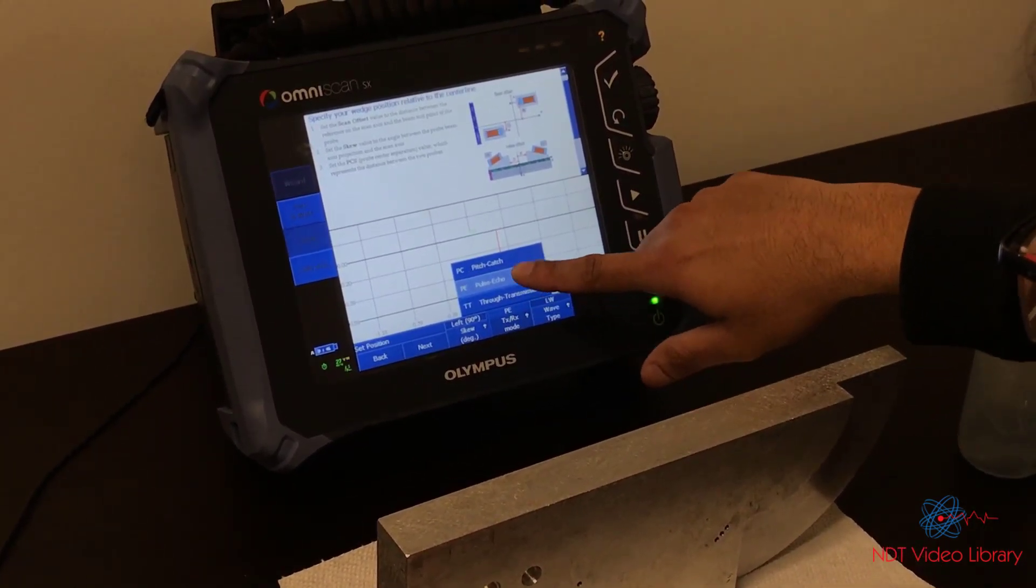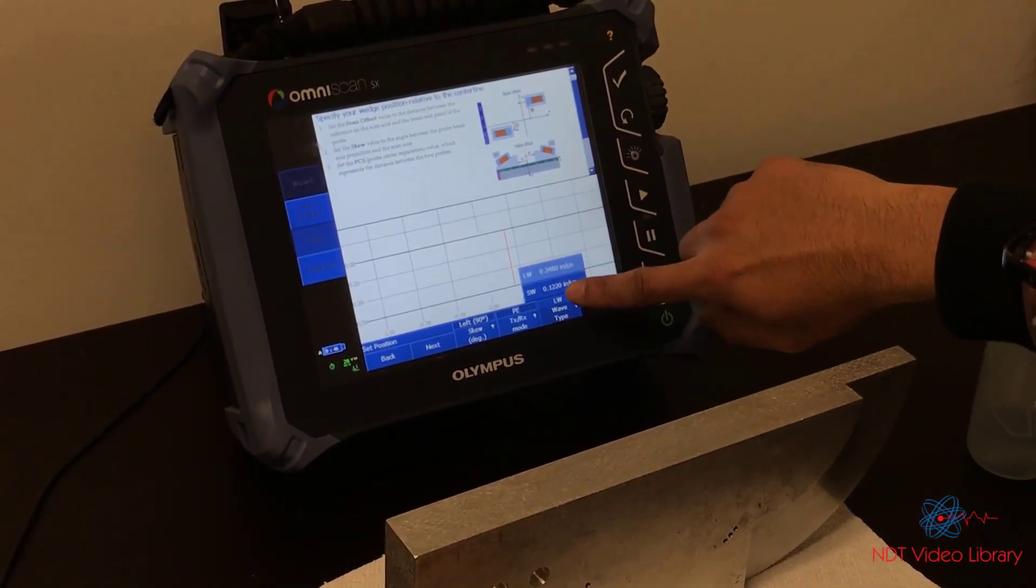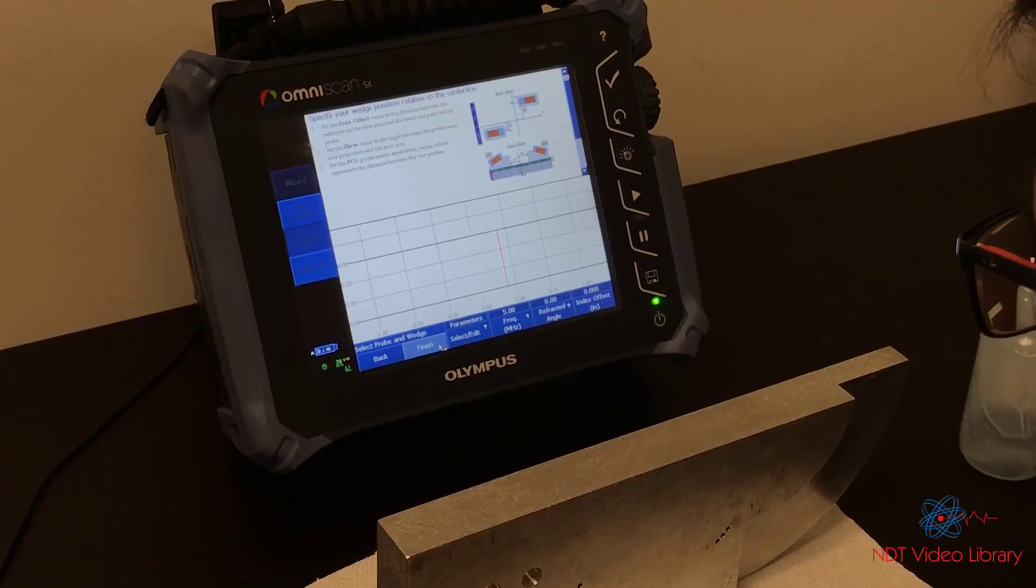Skew, we don't change it. This is pulse echo, single crystal, so PE. Wave type is going to be what? Shear wave. So we choose that. Next.